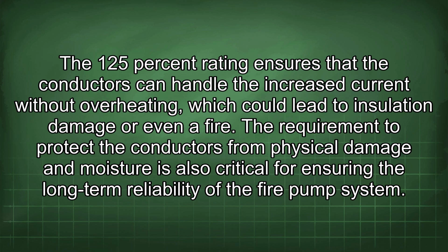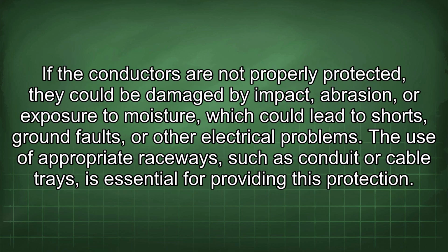The requirement to protect the conductors from physical damage and moisture is also critical for ensuring the long-term reliability of the fire pump system. If the conductors are not properly protected, they could be damaged by impact, abrasion, or exposure to moisture, which could lead to shorts, ground faults, or other electrical problems. The use of appropriate raceways, such as conduit or cable trays, is essential for providing this protection.